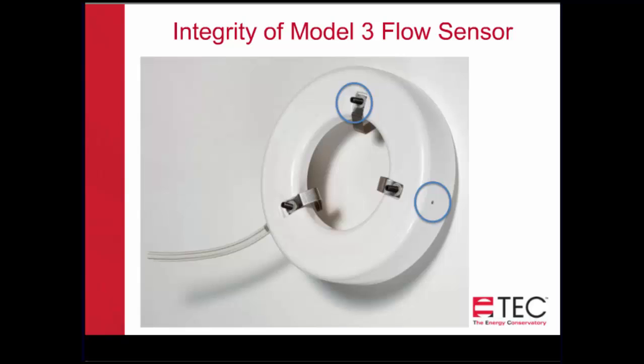The three screws that you see there are screws to adjust how far away from the motor the pressure sensor is. So you're able to adjust it up and down to move the pressure sensor either closer or further away from the fan in order to get the flow sensor in its proper location. I'll show you the measurement process in a moment.